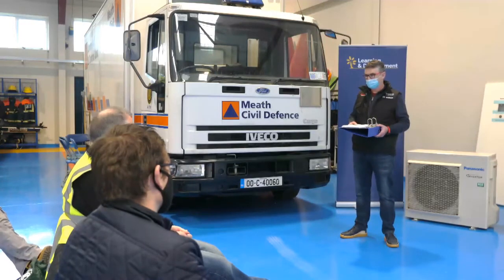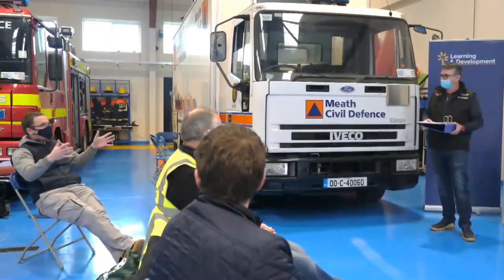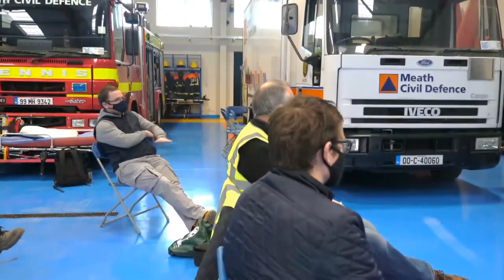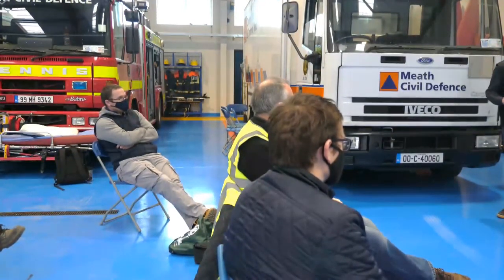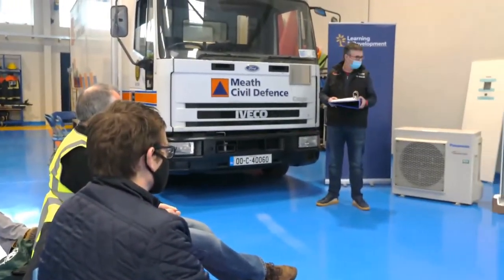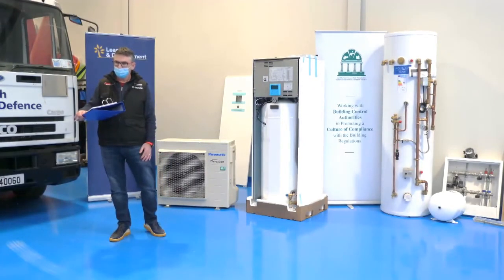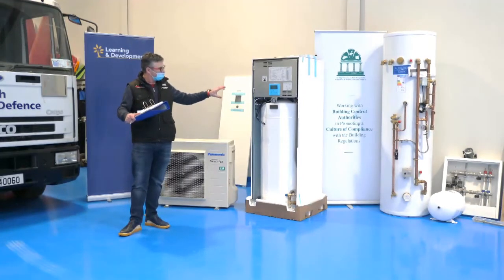In relation to the internal units, whether fitting it within an existing hot press or cupboard or freestanding, is service access down the line purely needed? There's a minimum clearance because you don't want to butt it up against the wall or another press, simply because of vibration and noise. But everything can be maintained from the front, right? Yes, you're getting right into the front, so that's all you need. Key things with the expansion vessel again: it shouldn't be more than 600 mil away from this unit.